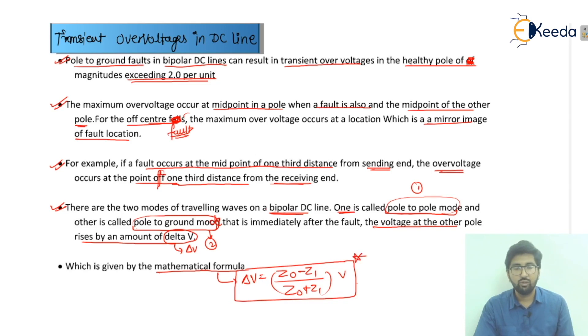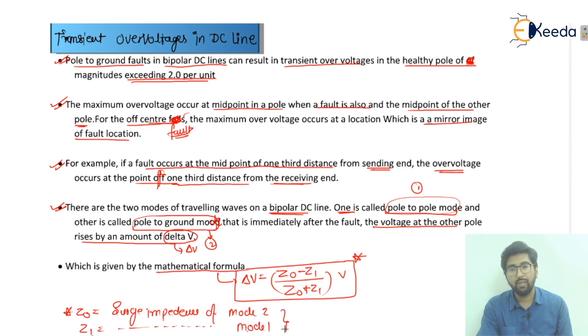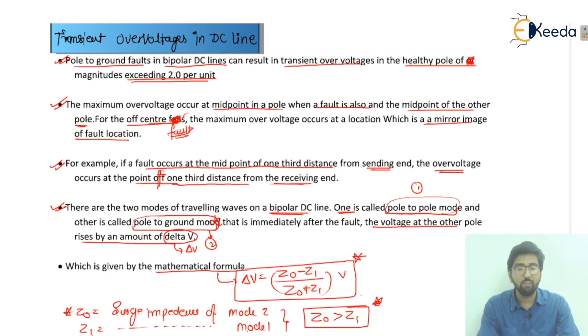Z0 is the surge impedance for mode 2 (pole-to-ground mode) and Z1 is the surge impedance for mode 1 (pole-to-pole mode). An important relation to remember is that Z0 is greater than Z1 — the surge impedance for mode 2 is more compared to the surge impedance for mode 1. Delta V represents the change in voltage, i.e., how much the voltage will rise due to the traveling wave.